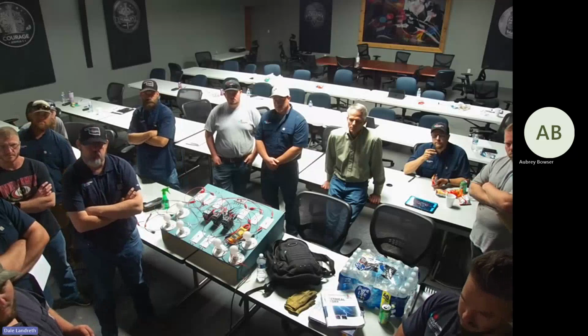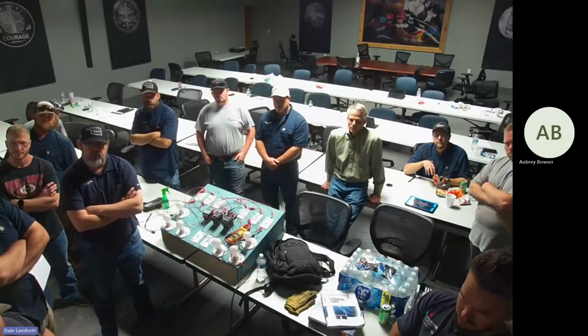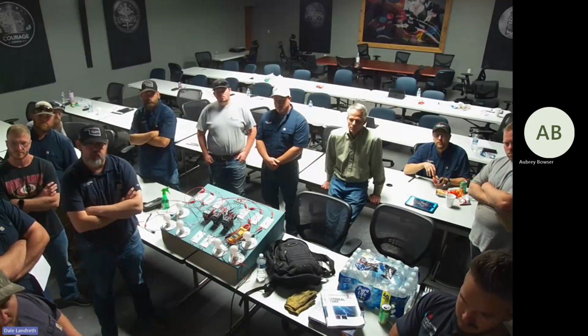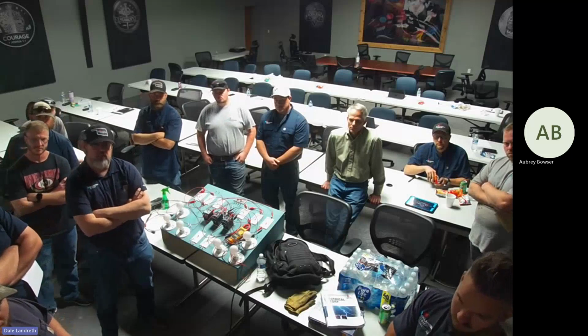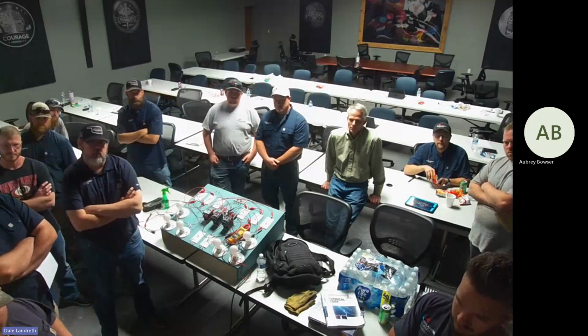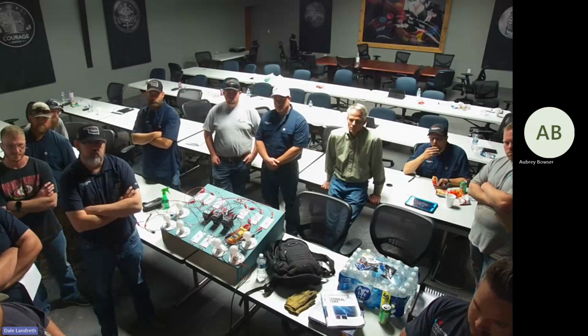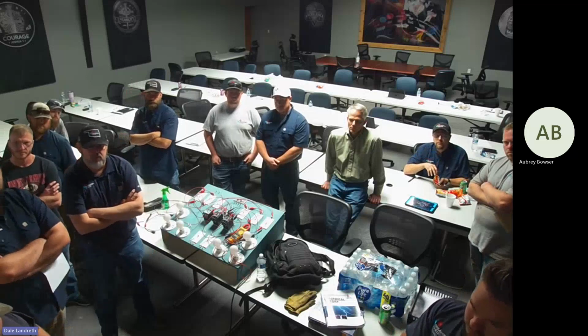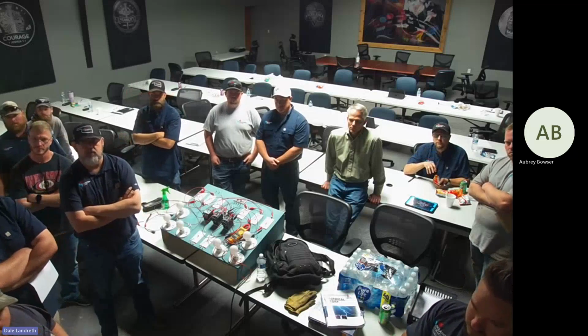Right now, if this compressor goes out—if it opens up on either of those switches, which are open right now—does that condenser fan motor still run? It still runs, right? Do we need it to run? So where else could we put it? Where else could we bring power for that?